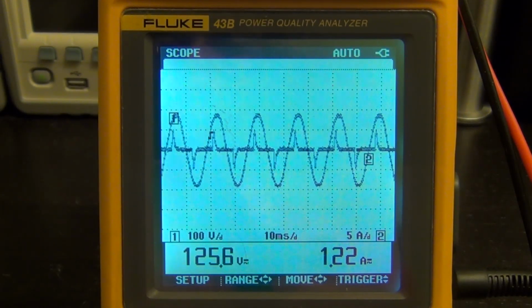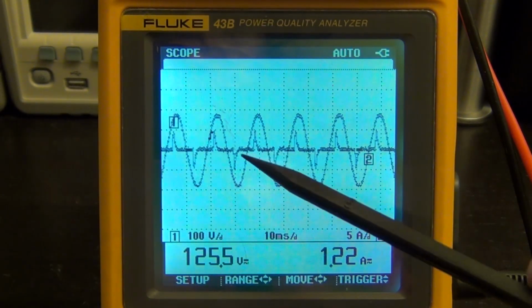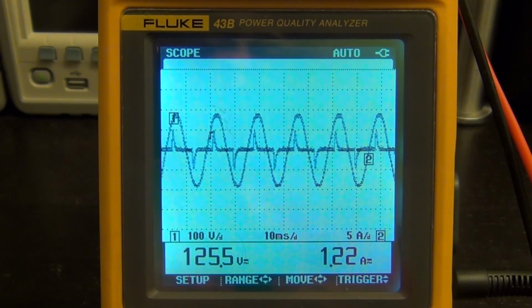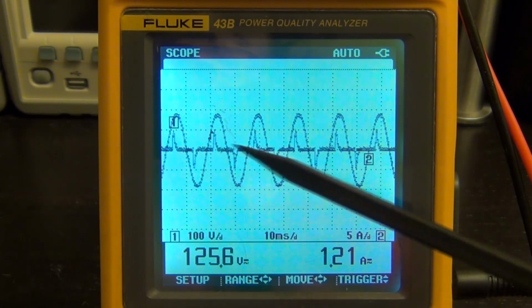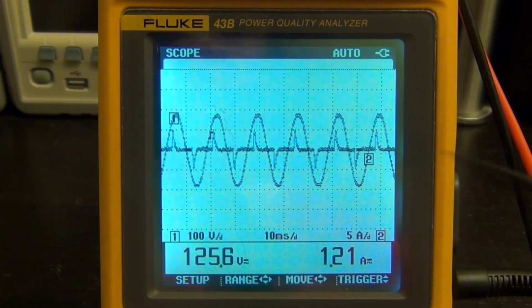There are two characteristics. First, the peaks lead the main peak of the voltage ever so slightly, so you have some leading of the current to the voltage. And the sharp pulses mean this current measurement is going to have a lot of harmonics in it, because it takes a lot of harmonics to produce a waveform with these positive and negative pulses.